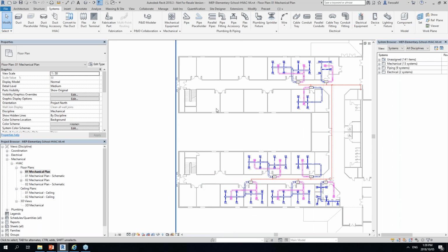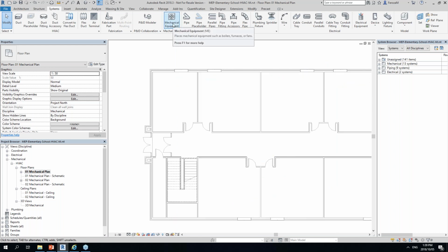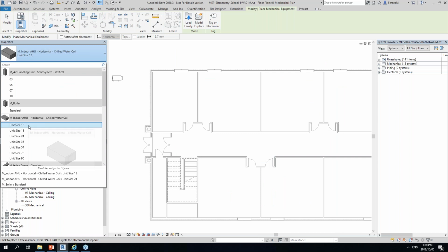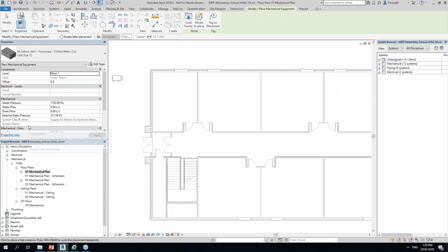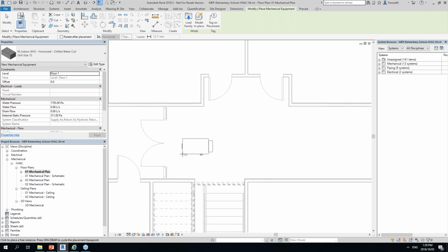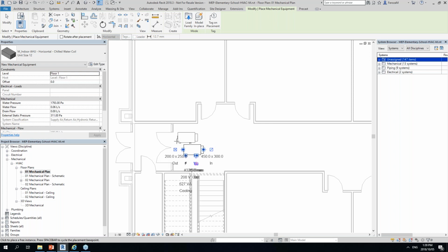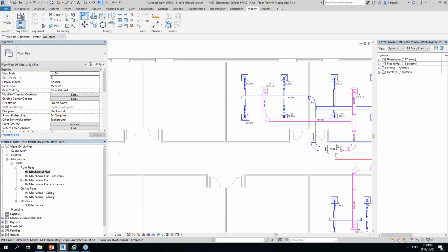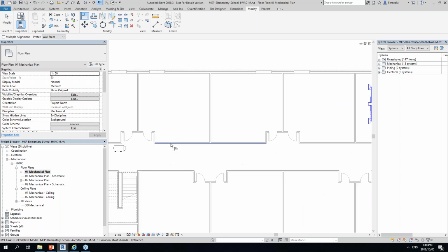All right, so I'm going to go over here. Then under my systems tab, under the mechanical panel, I'm going to click on mechanical equipment. And what I'm going to do is select a chilled water coil, which is the size 12, and place it here. All right, I want to align it to the one on the right side.